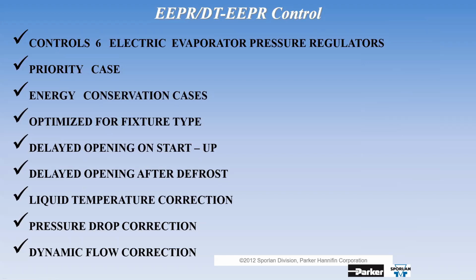Well, if 2 circuits come out of defrost, that's a massive load that we're sending down the line to the mechanical room. That might cause extra compressors to kick on, okay? Why make all 6 compressors kick on if I can slightly feather those EPRs gently back in, and I can then still hold it with only 3 or 4 compressors running rather than have all 5 or all 6 compressors.